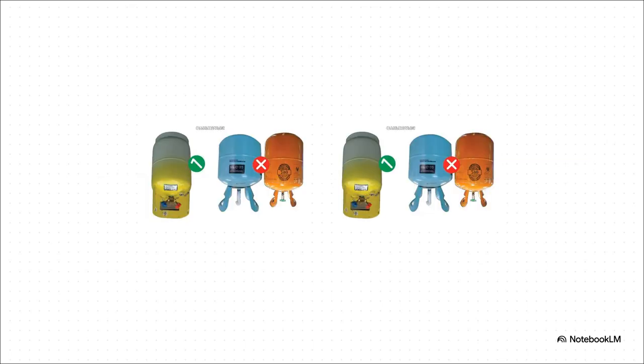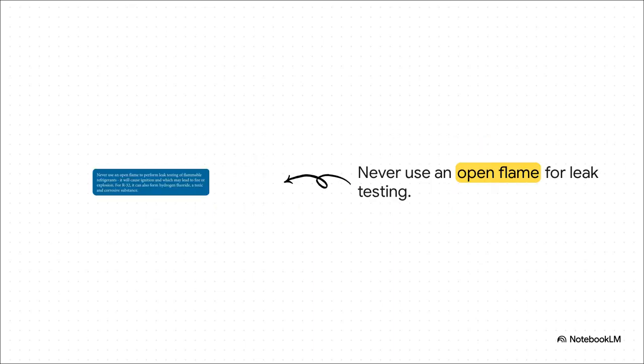Handling these new gases safely starts with proper containment. You absolutely must use the specific compliant cylinder for the exact gas you're recovering. The safety mechanisms, the pressure ratings, even the thread types differ wildly between an R32 tank and an R290 hydrocarbon tank. Putting the wrong gas in the wrong tank is basically a recipe for disaster. And please take this warning seriously. Never, ever use an open flame for leak testing on these new systems. Not only can it cause instant ignition and a literal explosion, but specifically with R32, exposing it to high heat or an open flame forms hydrogen fluoride gas. That is a highly toxic, corrosive substance that will cause severe respiratory damage if you inhale it. Stick to electronic leak detectors or bubble solutions, always.